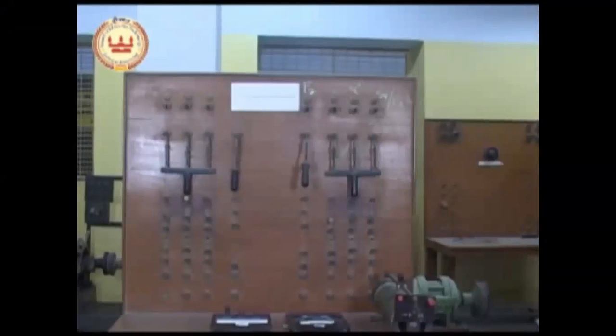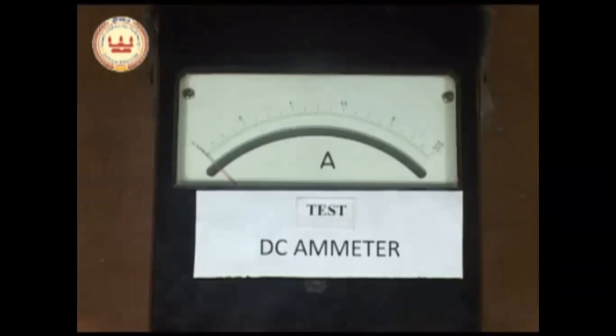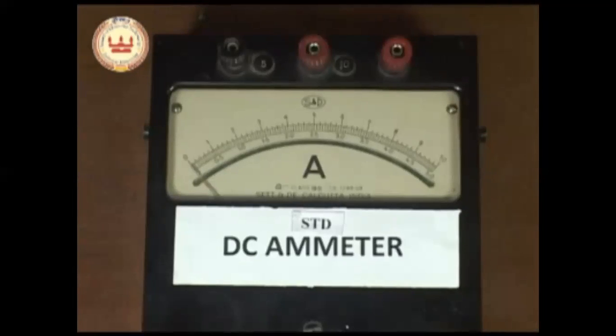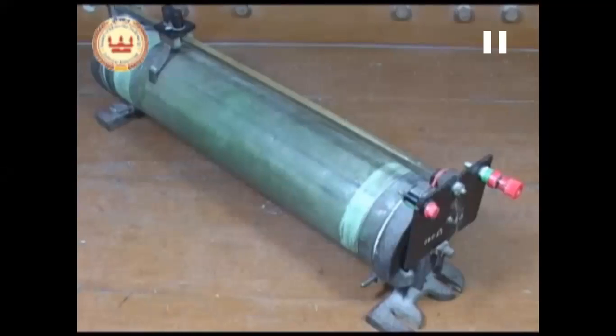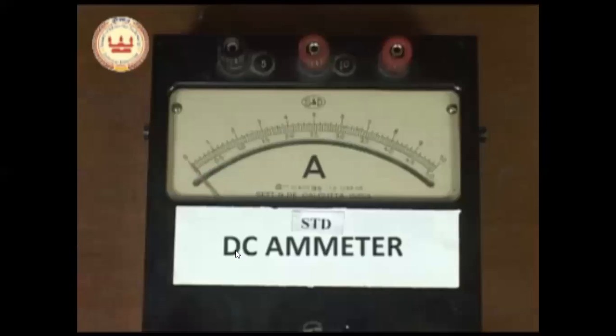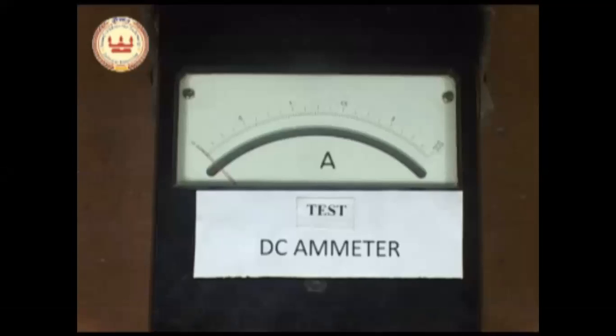Now let us connect these components for calibration of ammeter and voltmeter. First, let us have a look at the instruments for this experiment. This is a DC ammeter of range 0 to 2.5 or 5 ampere, and the next one is another DC ammeter of range 0 to 5 ampere or 10 ampere. Here you can see that the smaller range will be used for the test ammeter, that means this 2.5 and 5 ampere range will be used for the test ammeter, and the larger range will be used for the standard one.